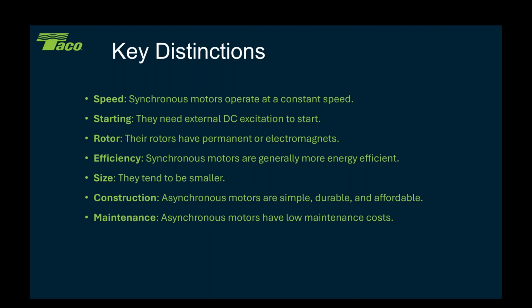The other thing that you will notice with permanent magnet motors is they weigh less. Since we've taken all that steel and copper out of the rotor and replaced it with rare earth permanent magnets, they weigh less, on average about 30% less, which is a good thing. We're always trying to figure out how to make equipment weigh less, because it's easier to handle, easier to maintain, and takes less structure to support that equipment. So making it weigh less is a good thing. Now, one of the things I have found, though, in talking to some of the cooling tower guys, is that on the very large frame permanent magnet motors, they've actually gotten bigger. So the motor itself is bigger, and they've had to do some redesign on some of their supporting structure to support those big motors.